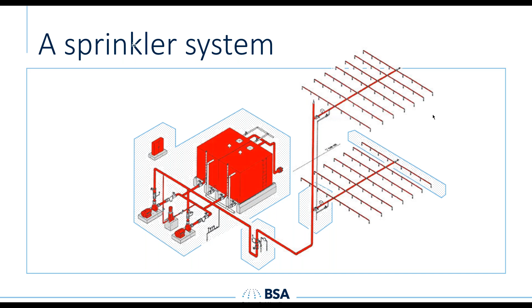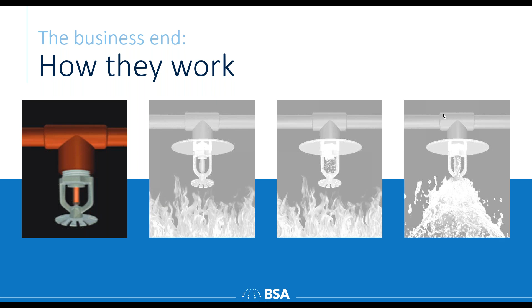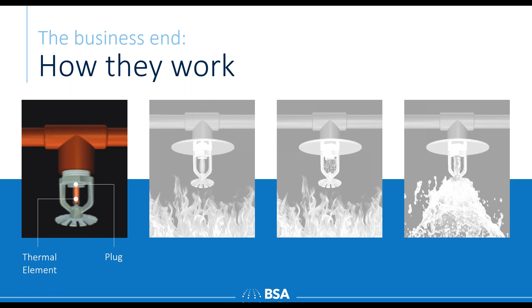The next element to talk about is really a sprinkler head. I know a lot of people have seen them, but just to combat some of the myths, it's good to go through the background as to how they work. The important parts of a sprinkler head are really two key objects. One is that in all sprinkler heads you'll see a thermal element. A thermal element is the piece that actually makes the sprinkler head respond to fire. In modern sprinkler heads, that's typically a glass bulb filled with a liquid, and that liquid is sensitive to heat. That thermal element holds in place a plug, and the plug is there to hold back the pressurized water. So if the thermal element breaks for some reason, nothing will hold the plug in place and the water flows out. And that's the simple premise behind the sprinkler head.